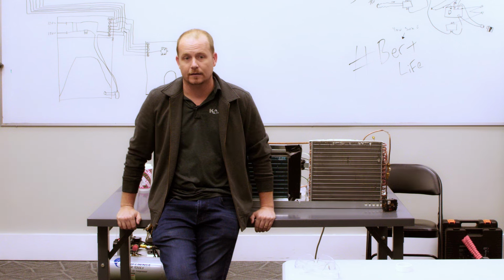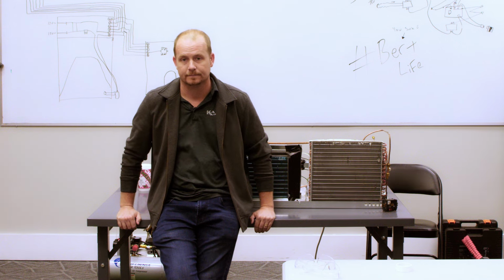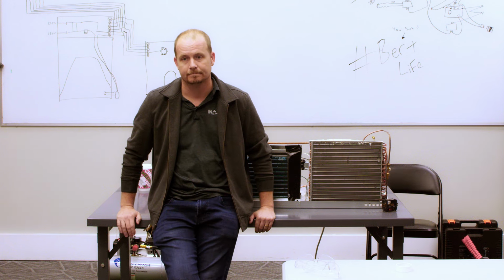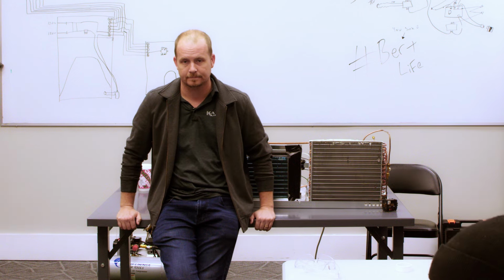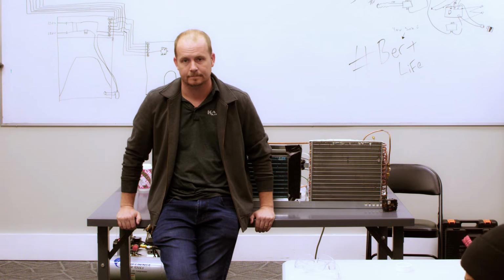Okay. Which is interesting for me because as we're trying to fill up that condenser, the temperature outside changes consistently. So our subcool's not always going to be 10. So say we set it to 10 on startup, based on the temperature, that number is going to change.